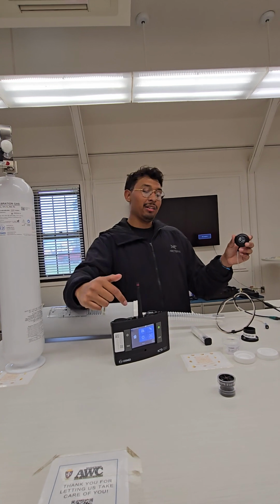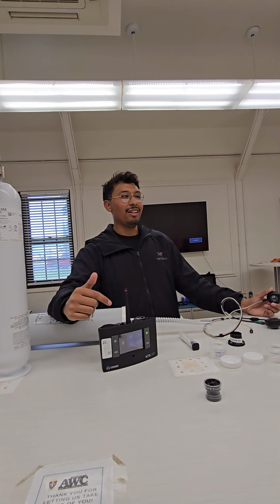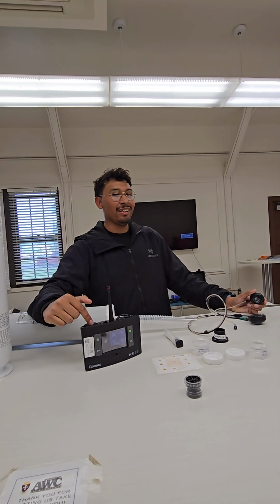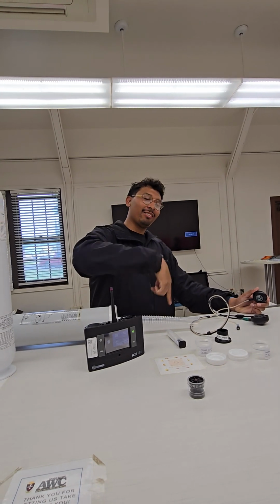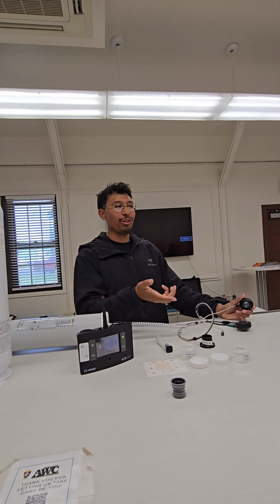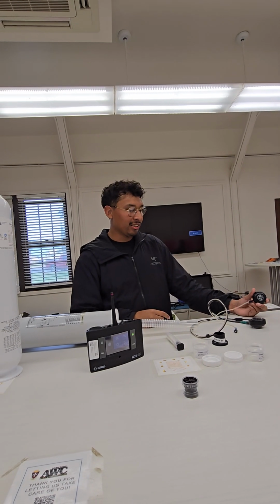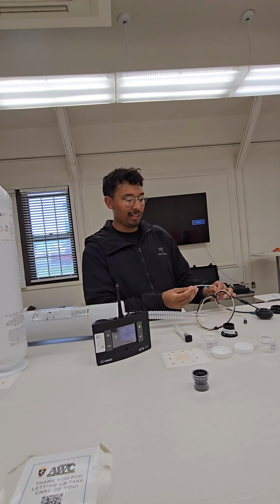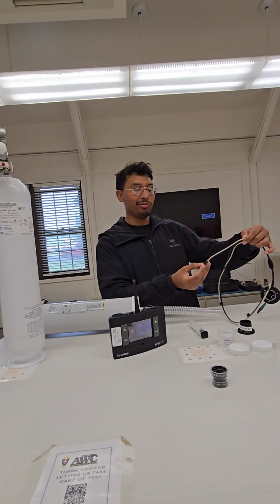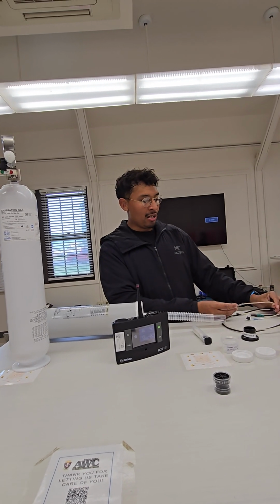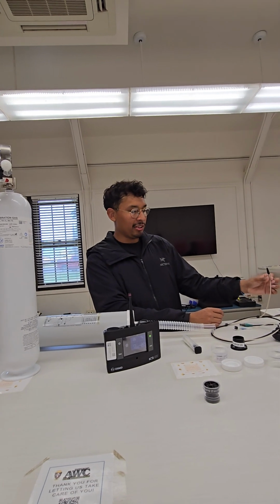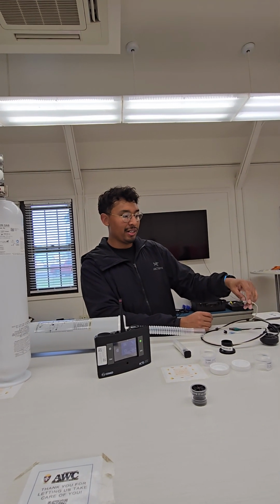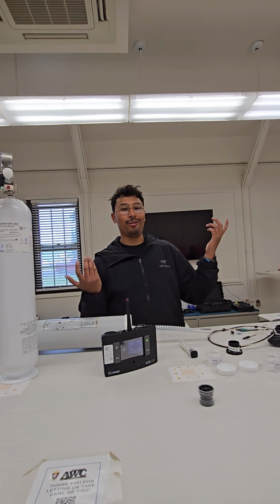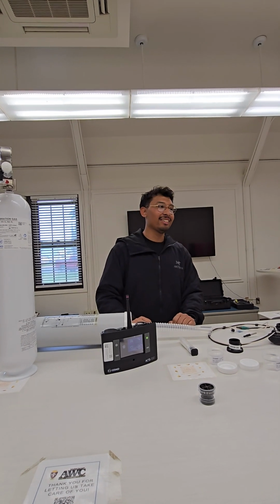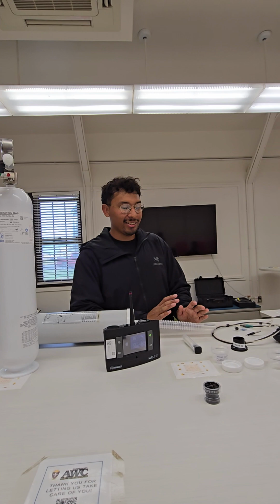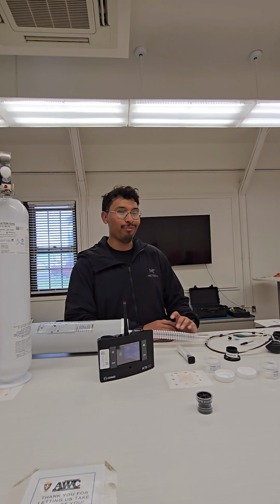The sample that's being brought into the analyzers needs to be down to room humidity before it gets to the analyzer. When someone is breathing, it's 100% humidified. So it's just really sensitive to humidity, and that's why they turn super brown. When they're new, they're basically clear. So just try to take care of them as much as you can. Place them in plastic bags if you can, and obviously we're in Hawaii, so humidity is probably insane all the time. But just try your best to keep it away from humidity.